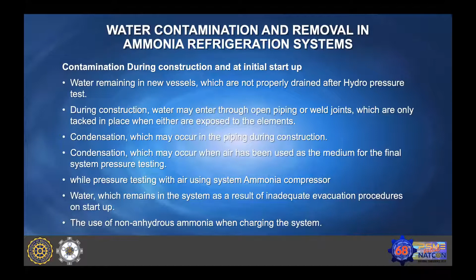And when the plant is running, there is a possibility that on the low pressure side, the tubes may get ruptured, like in shell and tube heat exchangers or ice bank tank coils. That directly connects the ammonia to the water, and water will enter. Also, while draining oil from the refrigerant systems or vacuum pipes, sometimes water may enter.